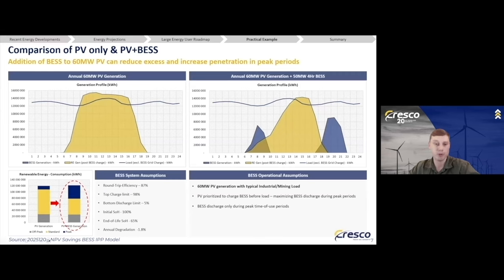penetration in peak periods. And the main benefit of BESS is not that it increases generation. The gross annual generation remains roughly the same, although there are some round-trip efficiency losses, which is taken into account. But nonetheless, the BESS increases the value per megawatt hour just by shifting consumption into the peak tariff window, like you can see in the bottom left figure.